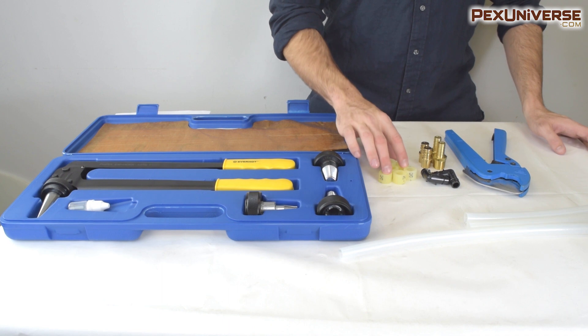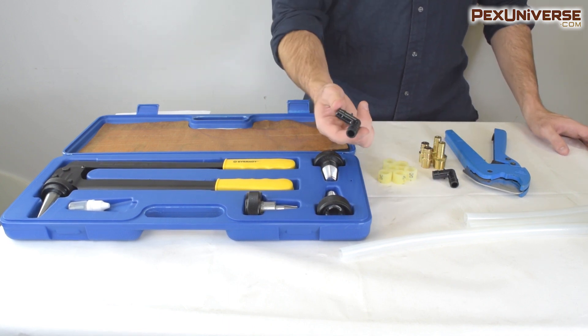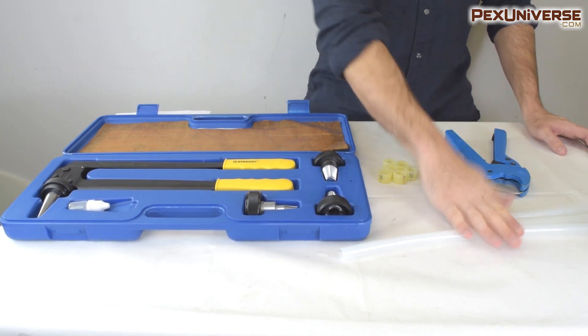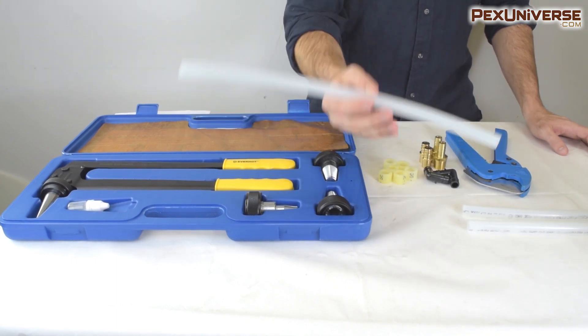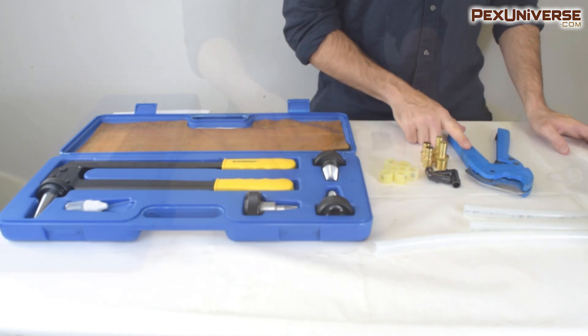These are expansion rings. Here's your expansion fittings - this is poly alloy and this is brass. PEX tubing. It has to be PEX A because PEX B will not fix itself after you expand it. And these are PEX tubing cutters.